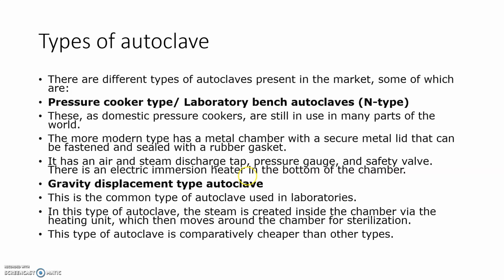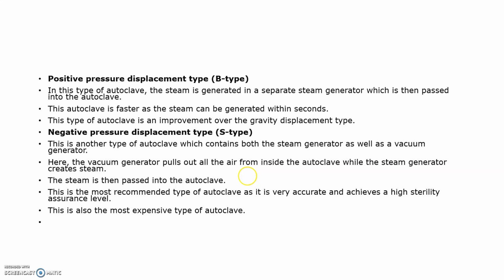Next type is the gravity displacement type autoclave. It is a common type used in laboratories. In this type of autoclave, the steam is created inside the chamber through a heating unit, which then moves around the chamber for sterilization. This type of autoclave is comparatively cheaper than other types. Gravity displacement type autoclave.